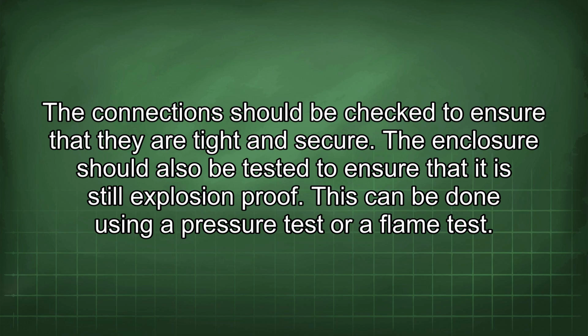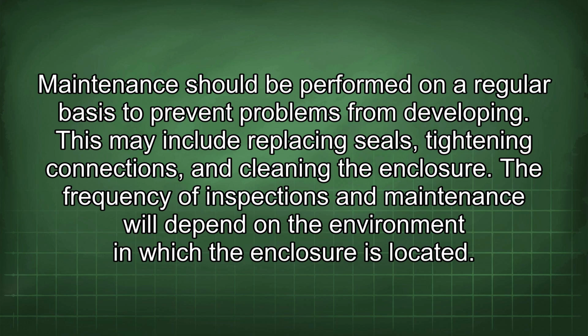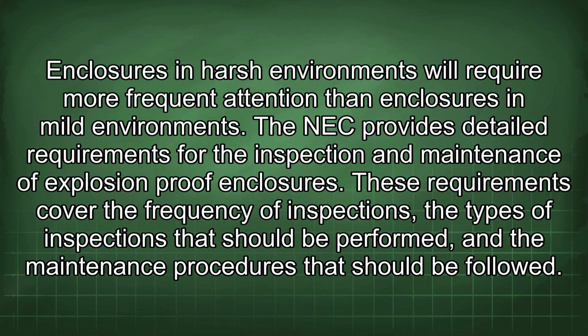The enclosure should also be tested to ensure that it is still explosion-proof. This can be done using a pressure test or a flame test. Maintenance should be performed on a regular basis to prevent problems from developing. This may include replacing seals, tightening connections, and cleaning the enclosure. The frequency of inspections and maintenance will depend on the environment in which the enclosure is located. Enclosures in harsh environments will require more frequent attention than enclosures in mild environments. The NEC provides detailed requirements for the inspection and maintenance of explosion-proof enclosures. These requirements cover the frequency of inspections, the types of inspections that should be performed, and the maintenance procedures that should be followed.